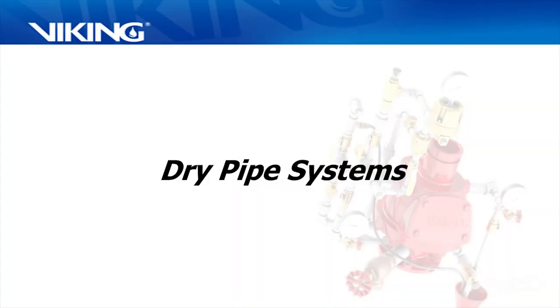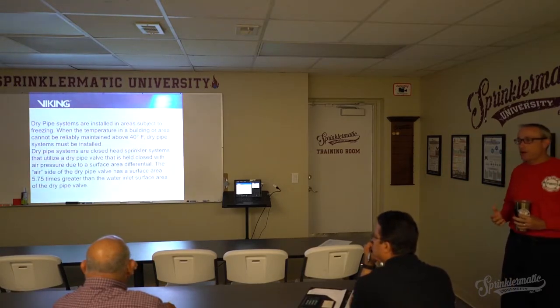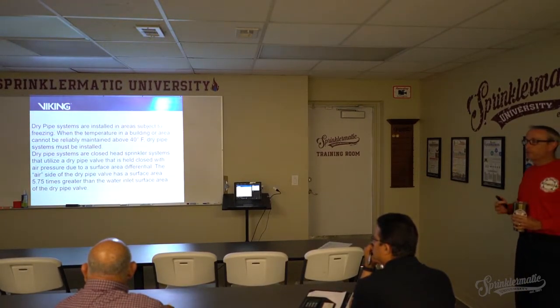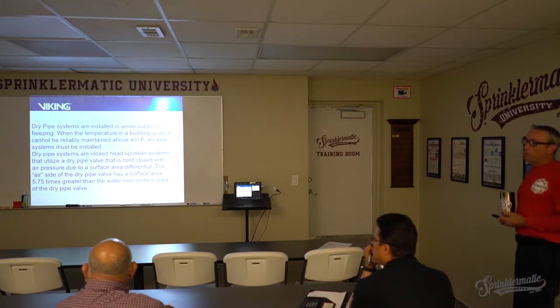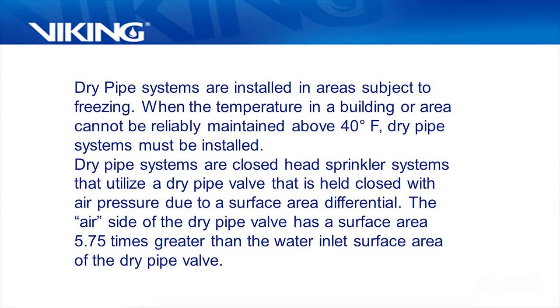This is the third class, and we're going to talk about dry pipe and preaction systems. The whole premise of fire protection is that we want the system to be automatic, and we want the system to be wet. That's the most preferred thing that we could do. Unless we're concerned with accidental water, which is where you're going to have preaction. But when you can't do a wet system, then you have to do dry. NFPA tells you that if you can't keep the temperature maintained in the area or outside above 40 degrees, then the dry pipe system must be installed.